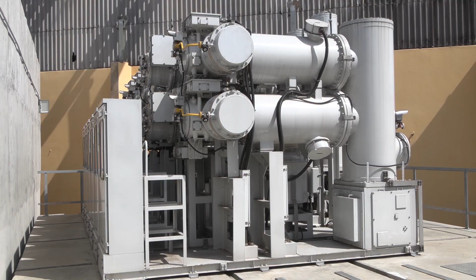In continuation of the electricity transmission capacity expansion goals, the Transmission Company of Nigeria, TCN, has successfully energized 2 units of 60 MVA power transformers and their associated gas-insulated switchgear, GIS, at the newly rehabilitated Apapa Road 132-33 kV transmission substation in Lagos State. The Assistant General Manager, Ajah Sub-Region of TCN, Engineer M.O. Umezuike, supervised the energizing of the power transformer and provided more details about this completed project.